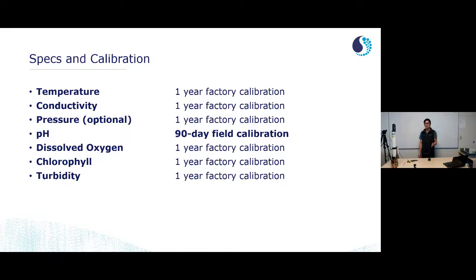However, the pH sensor, given that it is using this glass electrode technology, requires this 90-day field calibration. And so these are field swappable. You can have multiple of these, calibrate them in the lab, go out to the field, go out to your HydroCAT, and then replace them. It's a pretty quick process that I will demonstrate today.